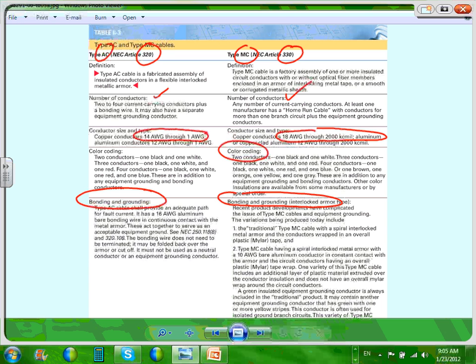The grounding conductor in an MC cable is a fully insulated green grounding conductor. In an AC cable, there's an aluminum bare bonding wire that comes with it. Then you have to wrap it on the shield of the conductor in order to get a solid equipment grounding conductor connection. So there is limited. That's where a lot of engineers don't like it, because of that little bare bonding wire.